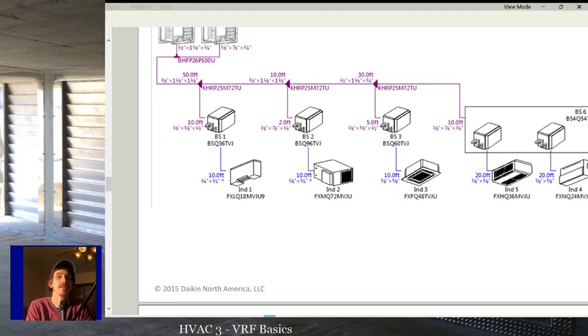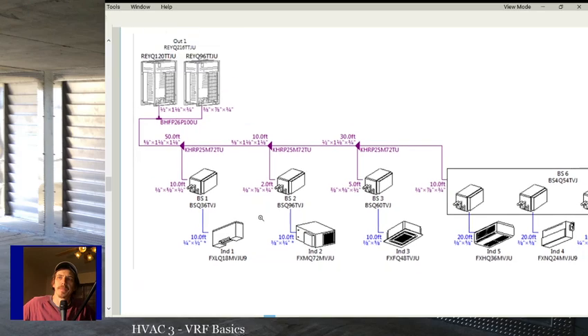The line that changes is the discharge line that can provide heat, may turn into a suction line. So if you ran it without a branch selector, and you tied it onto the discharge line and the liquid line, sometimes the unit would heat and sometimes it would cool. But you'd never know which it would be, because it all depends on what time of year it was. 90% of the time it would run in heating, and then at random it would run in cooling. So you can run a unit without a branch selector, but that unit is cooling only. Other than that, that's the basics of the piping.